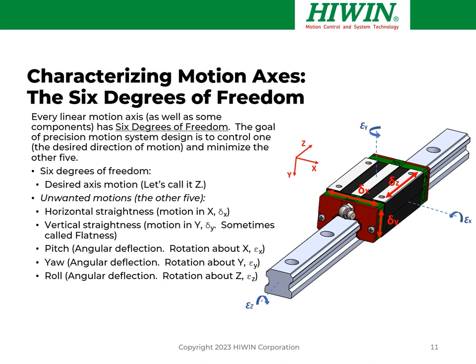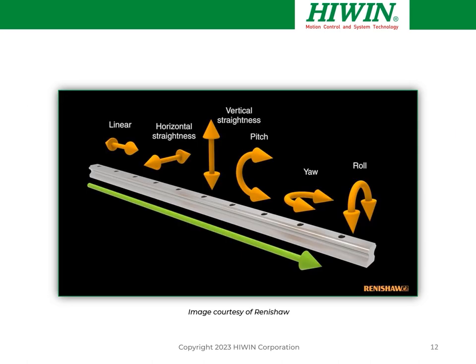The angular errors — pitch, yaw, and roll — are the ones that really add up and that we most want to minimize, because they especially contribute the most to Abbe errors. These are positioning errors caused by angular deflections in the motion system. Experienced motion engineers know how to design motion systems to minimize those errors. When you analyze all the errors in a multi-axis system, it starts to get really complicated. All of those components are used to form the error budget.